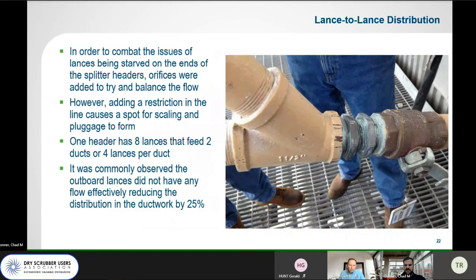So in order to combat some of those issues, in the past, the station has installed basically just a pipe reduction or an orifice to try and balance those flows and push more lime out to the outboard lances. But it was commonly observed, prior to this, that the outboard lances didn't have any lime flow at all. So if you've got 4 lances per duct, 8 lances per unit location, you're effectively reducing the distribution in the ductwork by 25% if you have 1 lance out of service or not receiving lime.